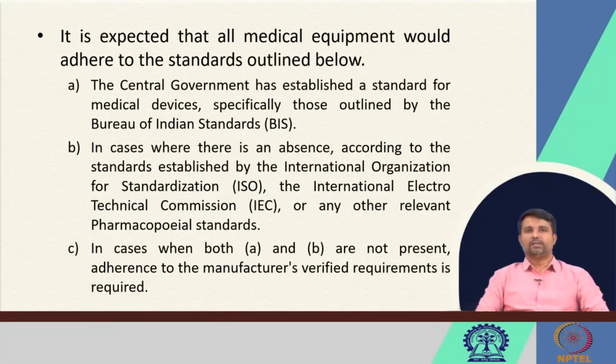It is expected that all medical equipment would adhere to the standards which are outlined in the Medical Device Rules 2017. The central government has established a standard for medical devices which are specifically outlined by the Bureau of Indian Standards. So, if BIS standards are available for a particular category of medical device, then all the manufacturers will have to follow the BIS standards. But there will be cases in which the BIS prescribed standards may not be available for a particular medical device.